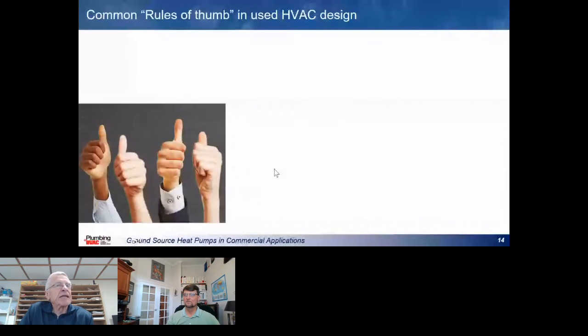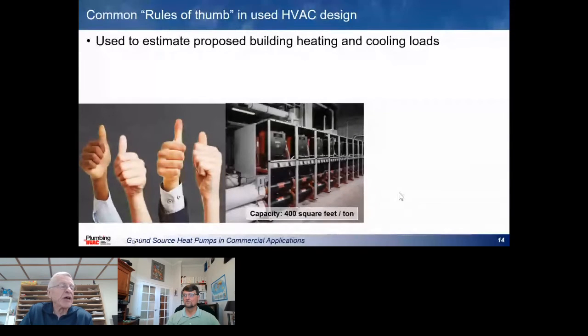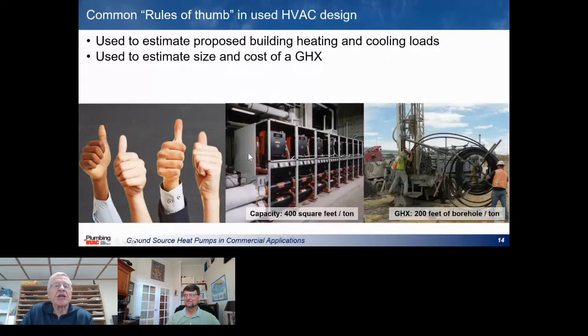In HVAC system design, you can get away with rules of thumb to estimate what the size of the equipment is. One common rule of thumb that I've heard over and over again is about 400 square feet of building per ton of equipment. And that's a fairly common rule of thumb, especially for commercial buildings. Another rule of thumb that's often used in the industry, and this varies a little bit from one region to another, is 180 to 200 to 220 feet of borehole per ton of equipment that you've installed in the building. And that's often used when a building owner comes to a designer and asks, is it feasible to install a geothermal system in my building? And for a quick number, this is often the kind of numbers that are used.